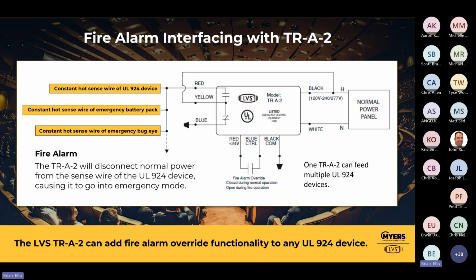If inspectors in your state are calling for this, you may run into something in the future where they say, we would love for you to provide battery packs and bug eyes, but have the fire alarm override them. And then you might ask yourself, how in the world do I do that? So we make a device called a TRA2. You feed it with utility, you run the utility through this normally open, right? So then what happens is, as long as power exists, then it's closed, providing power on the constant hot of any UL924 device that you may have, bug eye, battery packs, whatever. Then when utility fails, it would open, thereby turning all these devices to their emergency mode. But also, if utility is present, it allows you to connect to a fire alarm to be able to trigger the loss of power, even though we haven't lost utility. So if this is of interest to you guys or anything that we've talked about, please reach out to your RBM and we can get you more information if you're interested.